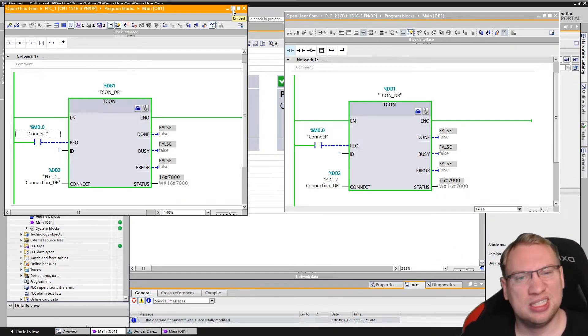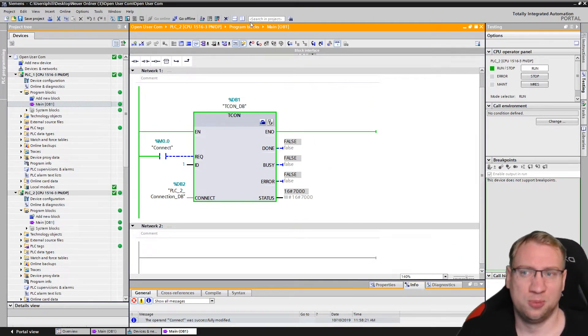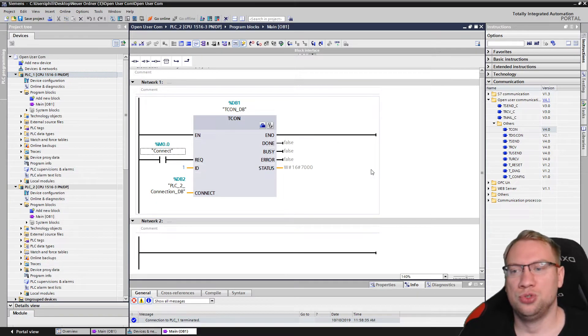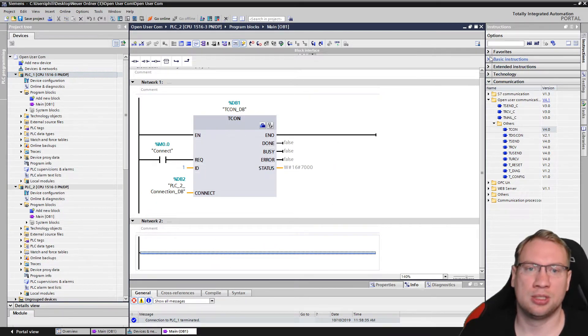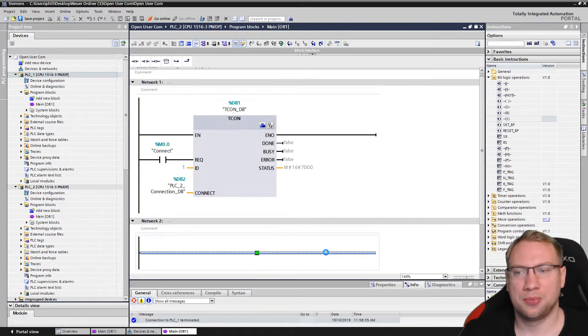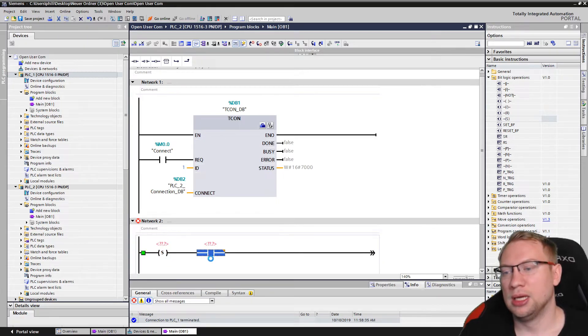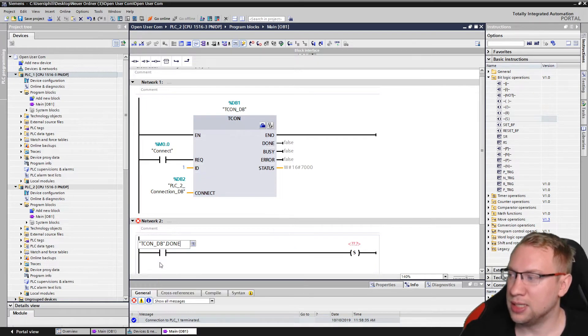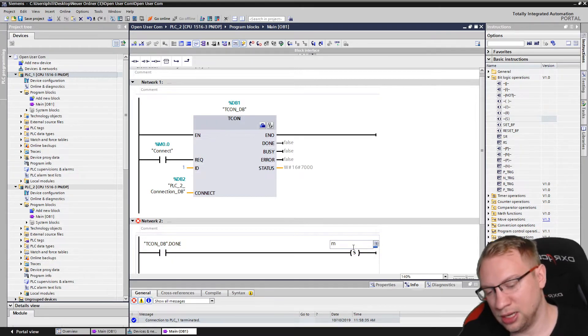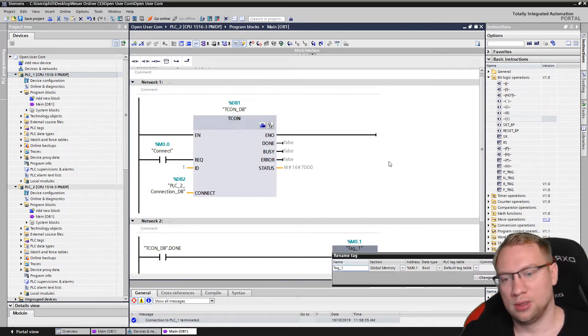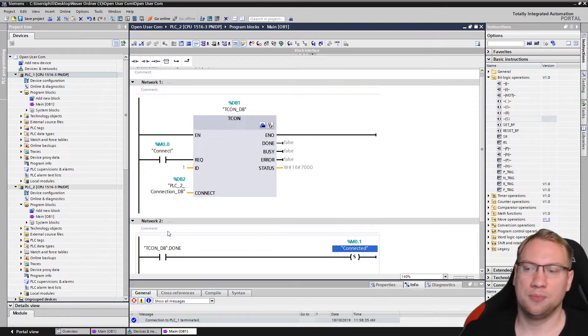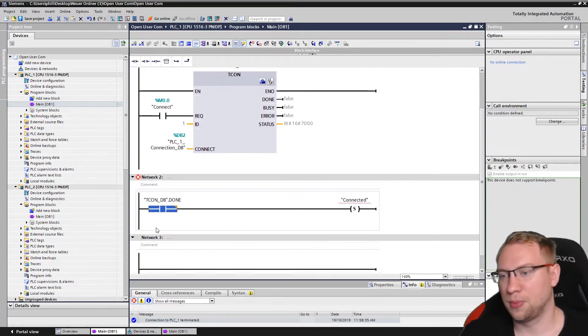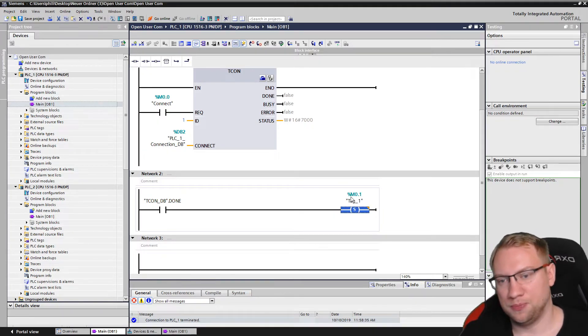The problem right now is I can't really see that we have this active connection — it's there but I can't really see it. Therefore, what I usually do is on a second network I add a simple set instruction: whenever the T-CON 'done' output is active, I set memory bit M0.1, which I call 'connected'. I copy this to my other PLC as well with M0.1.